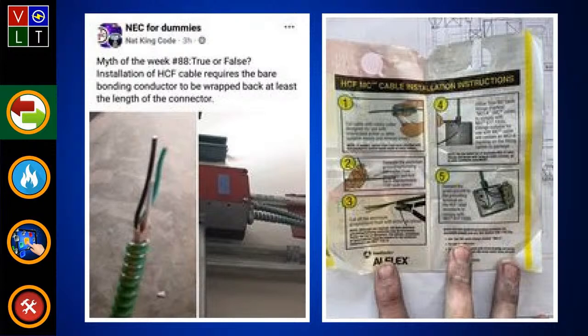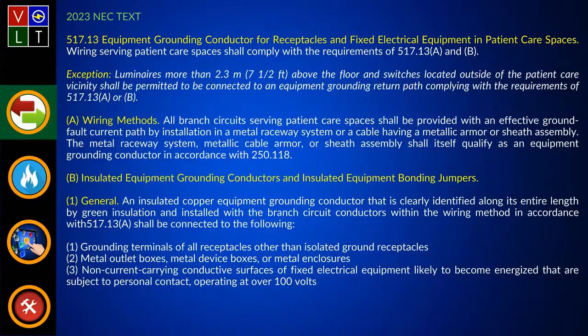And so basically, to comply with the healthcare facility requirements of 517.13 A and B, you need to have both of these paths. A lot of people call it a redundant ground, but it's actually required. What they're trying to do is decrease the impedance to open the overcurrent device faster, for patient care, for people in a vulnerable position who could be more susceptible to being shocked, where doctors are using powered instruments.